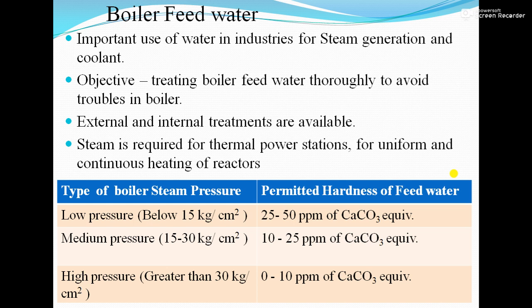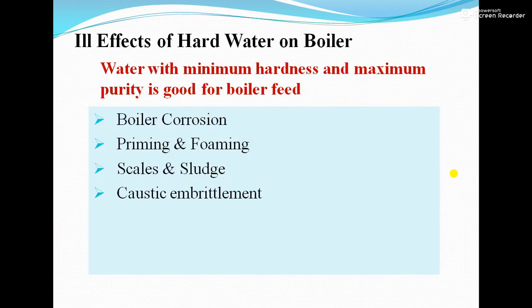If we use water which has hardness above 50 ppm or 100 ppm, then using hard water in the boiler causes bad effects on the boiler metals, such as boiler corrosion, priming and foaming, scale and sludge formation, and caustic embrittlement. Water with minimum hardness and maximum purity is good for boiler feed.